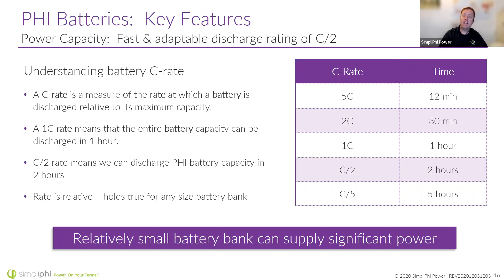As you add batteries, that rate holds true. It's going to scale up in power and energy capacity as you add these building blocks. We're able to scale our batteries up, meaning there's no limit to the number of batteries you can put in parallel. You can scale these batteries up to make the system size that you need. There's no communication lines to worry about, and you're scaling up in both energy storage and power throughput.